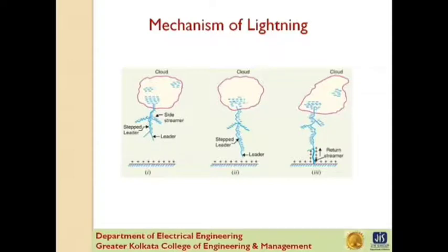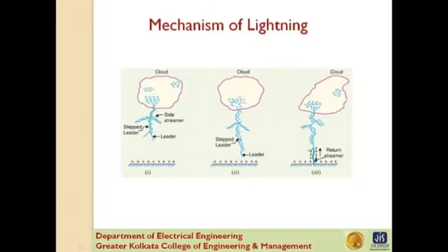The leader streamer will continue its journey towards earth as long as the cloud from which it originates has enough charge to maintain the gradient at the tip of the leader streamer above the strength of the air. If this gradient is not maintained, the leader streamer stops and the charge is dissipated without the formation of a complete stroke; in other words, the leader streamer will not reach the earth at all. It may be noted that the current in the leader streamer is low, less than 100 amperes, its velocity of propagation is about 0.05 times the velocity of light, and the luminosity of the leader is very low.